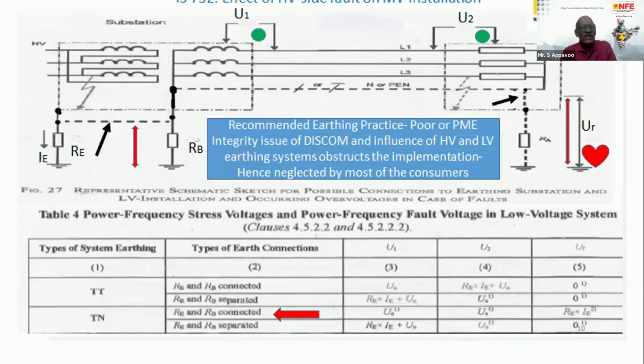For example, if the supplier is interconnecting this body as well as the neutral electrode, then that is the neutral of the LT system and the frame of his transformer. If there is a fault in the HT system or upstream of the HT line, then it will get transferred to the LT installations also. How? For various configurations of the LT earthing system, if you have a TN-S system, you will get shock, but our equipment will be protected when the supplier's earths are interconnected.